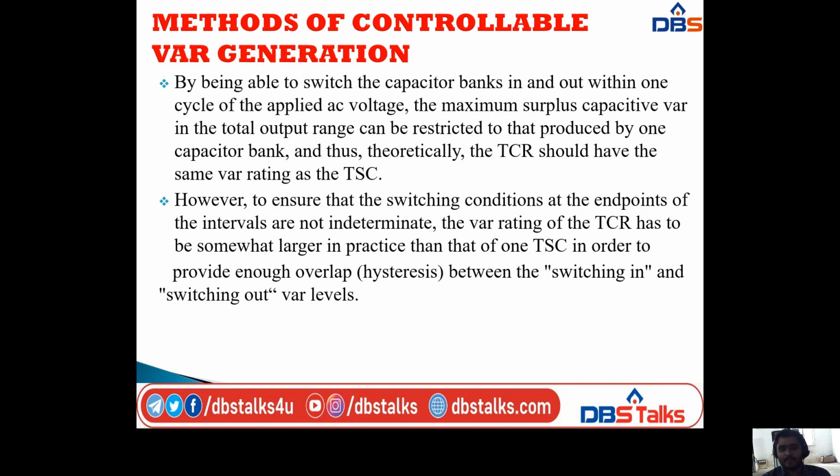Next, by being able to switch the capacitor banks in and out, that means connecting and disconnecting, within one cycle of the applied AC voltage, the maximum surplus capacitor VAR in the total output range can be restricted to that produced by one capacitor bank. And thus, theoretically, the TCR should have the same VAR rating as the TSC.